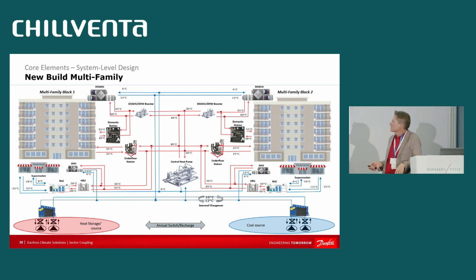But you'll also notice here that if you're going to supply a multifamily system, you don't want to repeat the problem with heating systems of the past. That problem was a design based on a top-down methodology: you produce all the heat needed for the whole facility, no matter the temperature demand, at the highest temperature demanded—high-pressure steam—and then valve and heat-transfer it down to lower temperatures.